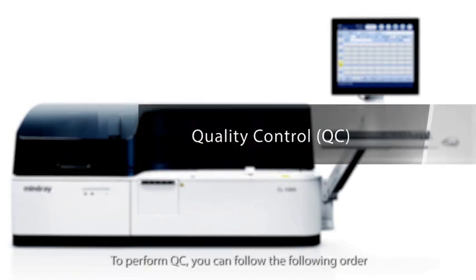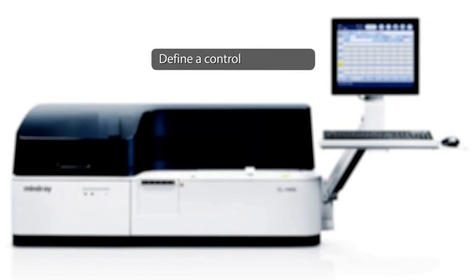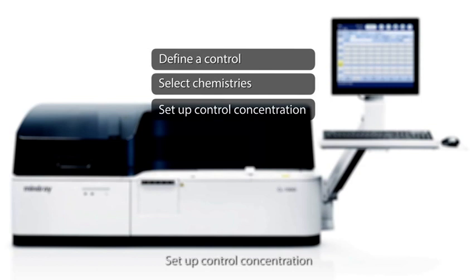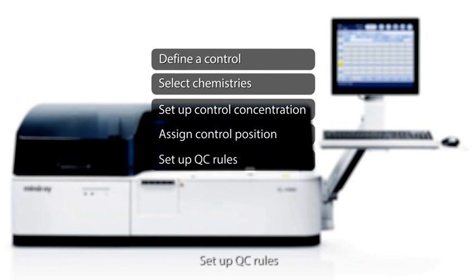To perform QC, you can follow the following order: Define a control, select chemistries, set up control concentration, assign control position, set up QC rules, run QC, and check QC results.